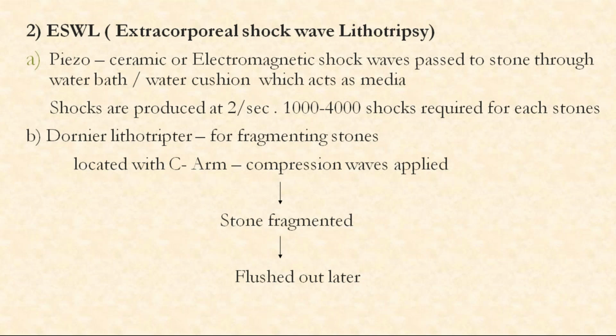The shock waves are produced every two seconds. A minimum of 1,000 shock waves must be given to each stone to break down the renal calculi.